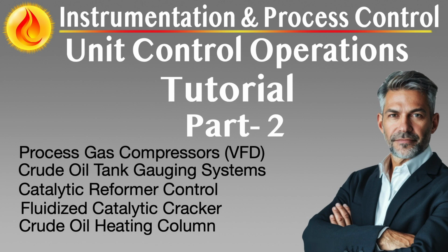The energy efficiency gains from VFD control are substantial. Since power consumption is roughly proportional to the cube of compressor speed, even small reductions in RPM yield exponential savings. In LPMP services, where compressors may operate far from design conditions for extended periods, VFDs allow operation near the minimum safe speed rather than at a fixed high speed with forced recycling. Real-time power consumption metrics and efficiency curves are now visible to operators via integrated dashboards, often tied into plant-wide energy KPIs or emissions reduction targets.